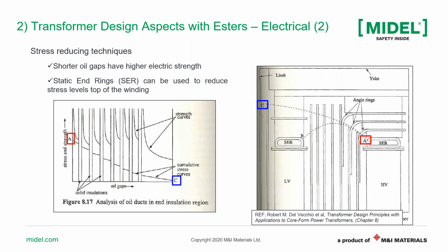On the y-axis, you have two lines. One is the stress and one is the strength. If you look at, I hope you can see my mouse, if you look at point A, you have two lines here, one line the stress, and the other line the strength. And our ideal thing is really, as a designer, to estimate the safety margin here. And when we are using a synthetic ester, this safety margin can reduce, and so sometimes a failure is caused. So with this, I hope to give just an overview of the impact of a different liquid on the transformer design.